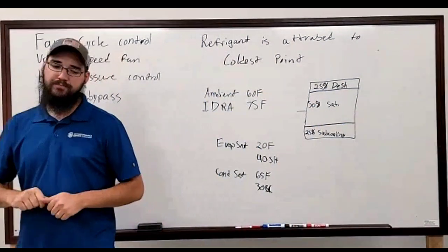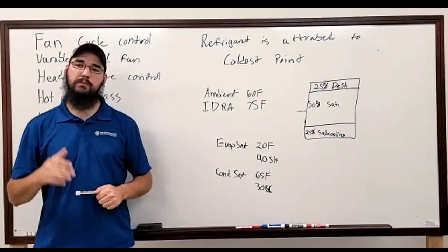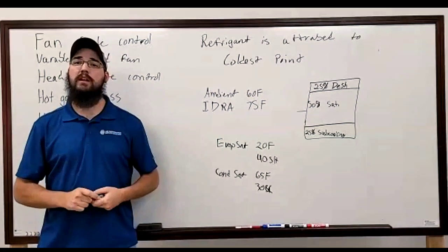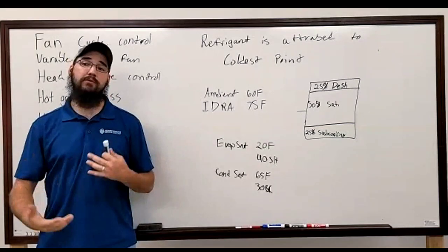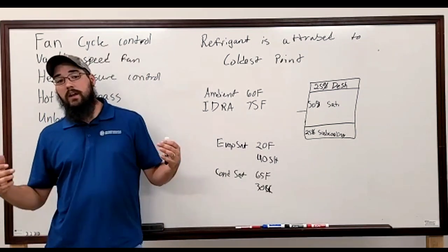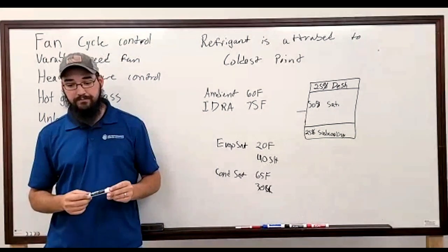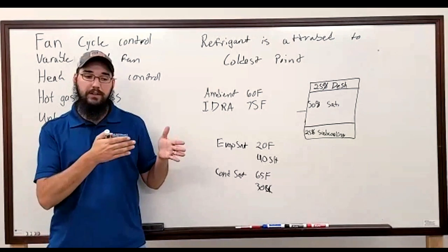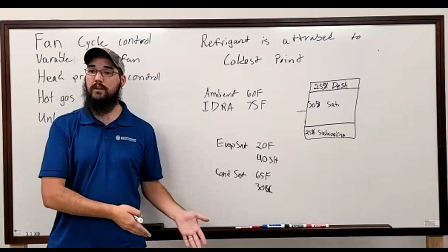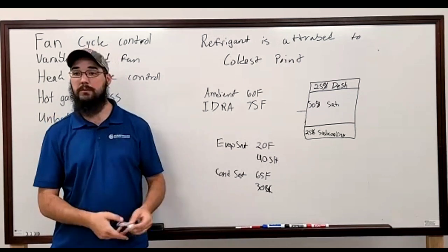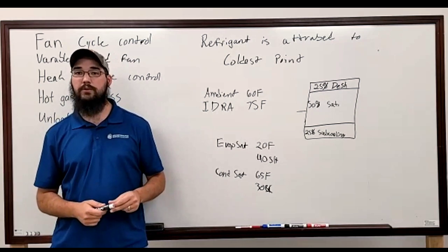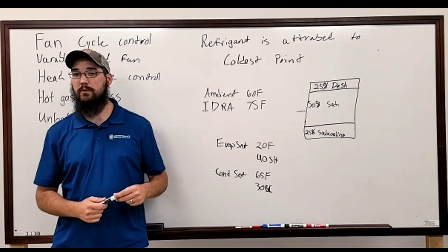I got a call Monday morning from a customer. We just put a brand new system in, and it has fan cycle control. And he went walking up to it, and they're very detailed, they're very routine, and they pay attention to their equipment. The customer calls me because the condenser fan motor wasn't running, but yet the condenser coil felt warm. It was hot to the touch. He could hear the compressor running, but the fan motor wasn't on.